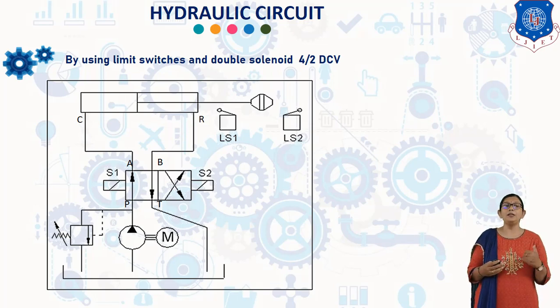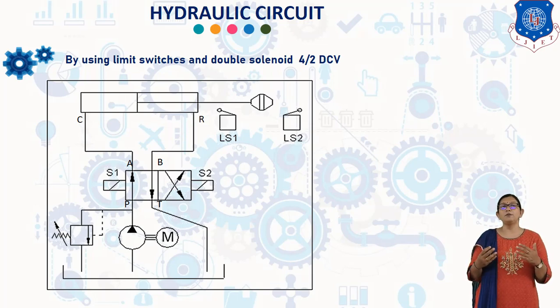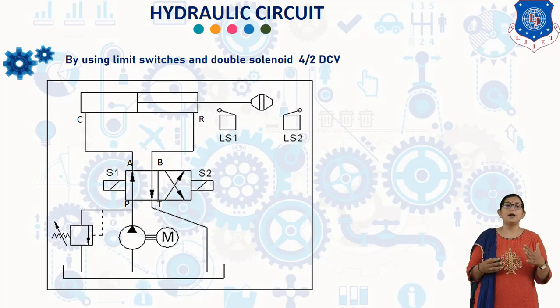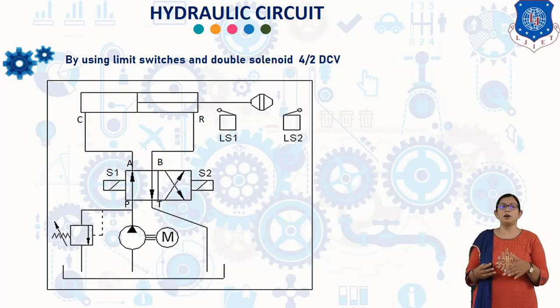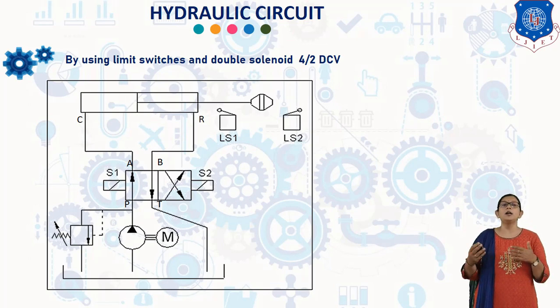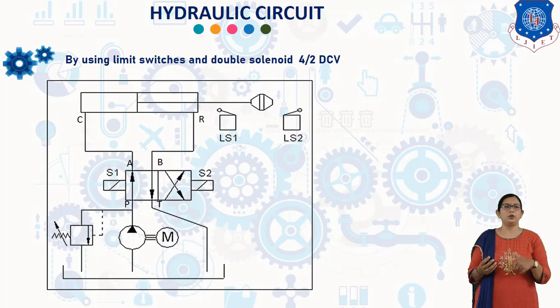In the second position of the 4/2 directional control valve, oil under pressure flows from P to B and A to T. Hence, the cylinder retracts. By the end of retraction, the cam presses the limit switch Ls1. The electric current flows to solenoid S1, and the spool of the 4/2 directional control valve shifts back to the first position. The cycle is then continued.